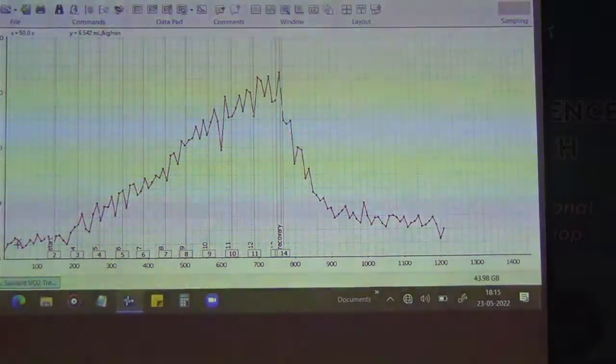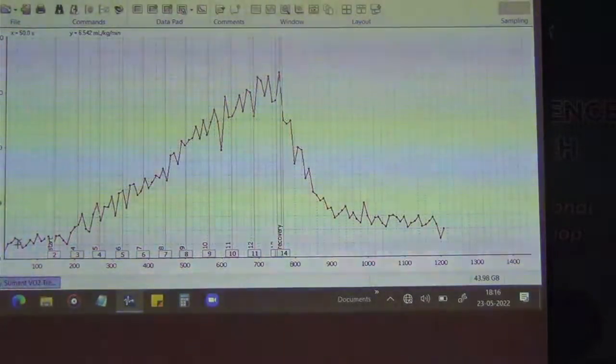The company may be different, but the principle and mechanism are the same. You inject the stroke, then it will automatically standardize and a message will come that volume calibration is successful. You have to accept the value. Then the last one is ambient temperature. You have to calibrate that. Once these 3 areas of calibration are done, you can go for the testing.